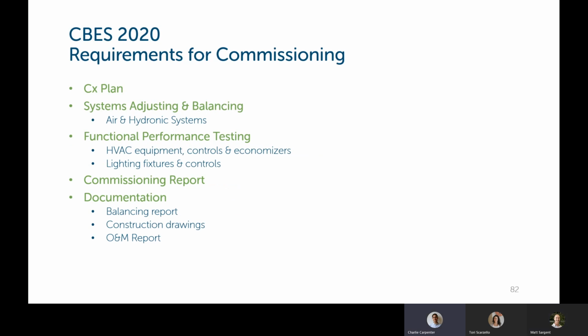Next slide. And these are just some of the requirements that are laid out for what you need from building commissioning. You've got to have a commissioning plan, systems adjusting and balancing plan for both your air and hydronic systems on the HVAC side, functional performance testing for your HVAC equipment, any of the controls tied to that equipment, and your economizers as well. Lighting's included in this as well, the fixtures and controls. You've got to have a finalized commissioning report where you document certain aspects, and also include that balancing report from earlier, any notes to the construction drawings that have been made from the commissioning agent, and an operations and maintenance report. All of this will be provided to the owner after it's been completed.